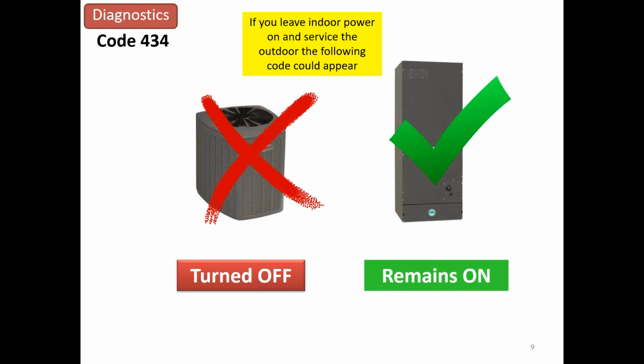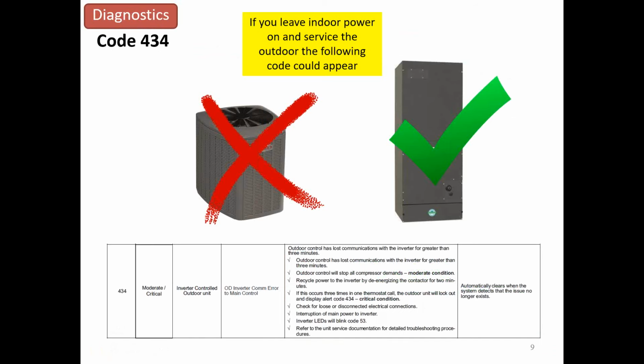This usually happens during the tune-up process. I'll get guys that go out and do a service on it, and they'll start shutting power off because we want everybody to be safe while they're doing a tune-up and spraying water and stuff. And they'll turn the outdoor unit off and then go in and so on and so forth. So this code comes up quite regularly. I get a phone call probably once a week on this code. So I like to bring that up just because I want to eliminate some of those phone calls from your team.